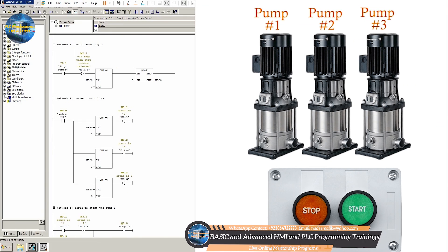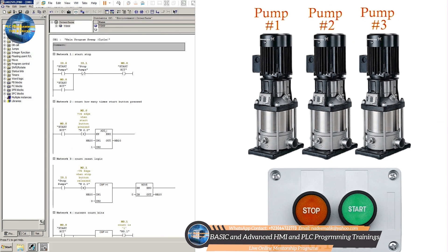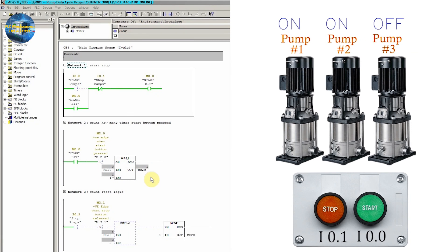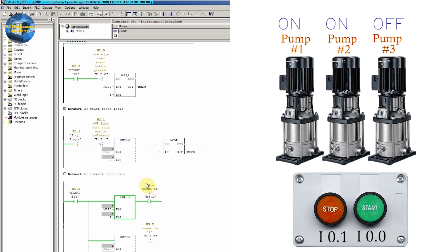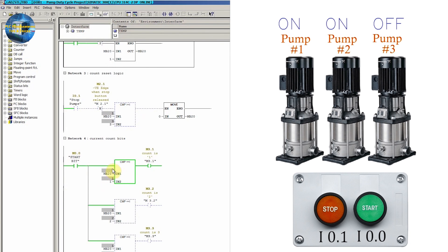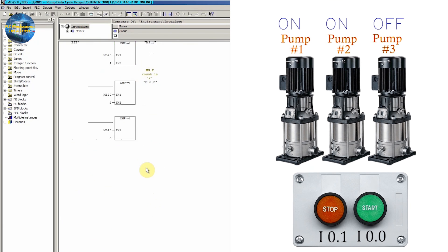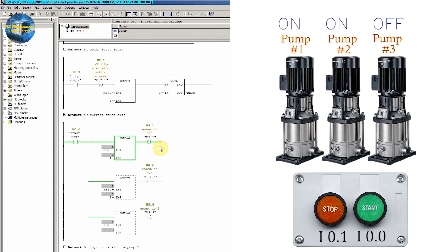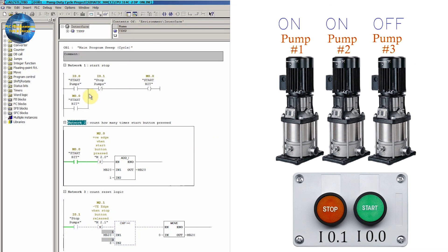Our logic is now ready. We will upload this program into the PLC and monitor the ladder logic. When we turn on start push button I0.0, it turns on M0.0 start bit. The count in MB20 is 1, the M3.1 bit is turned on, and it has turned on pump number 1 and pump number 2, Q0.0 and Q0.1.